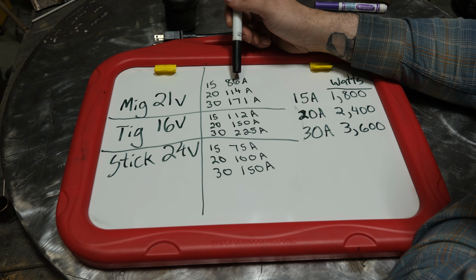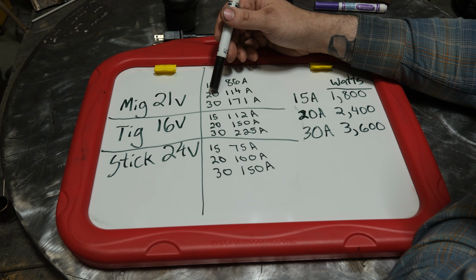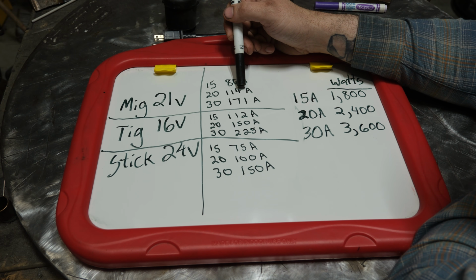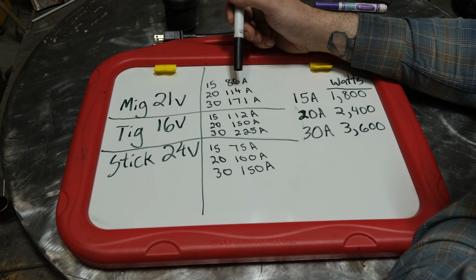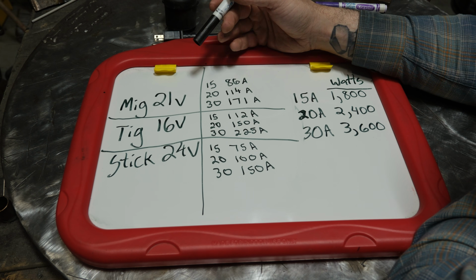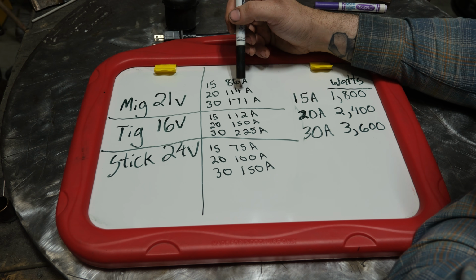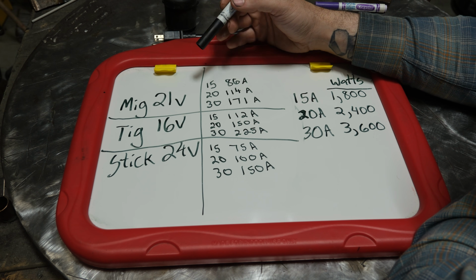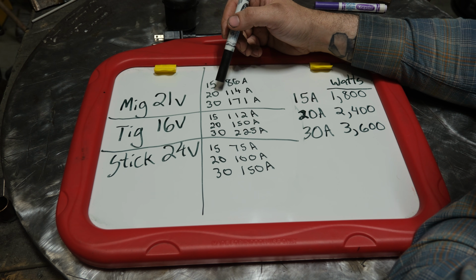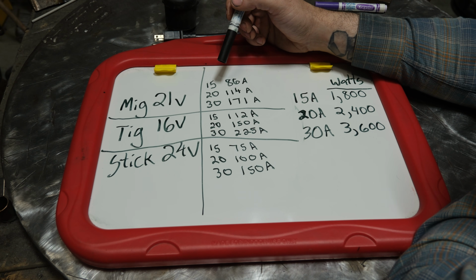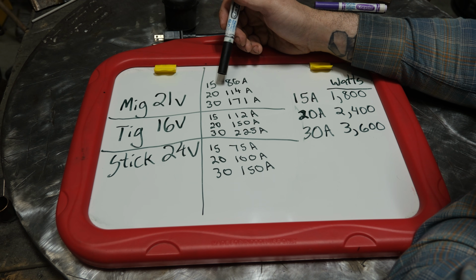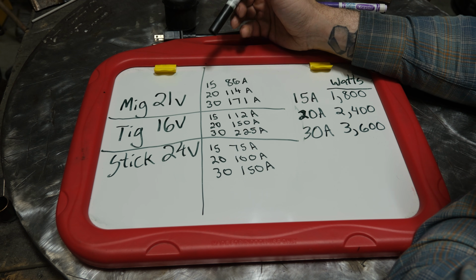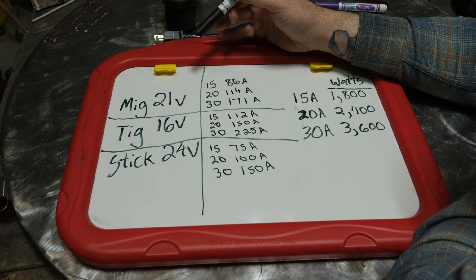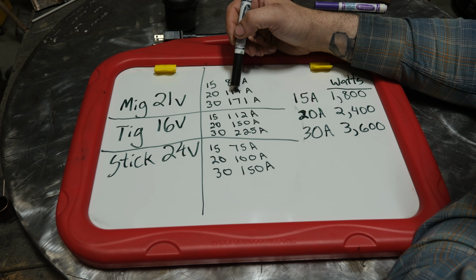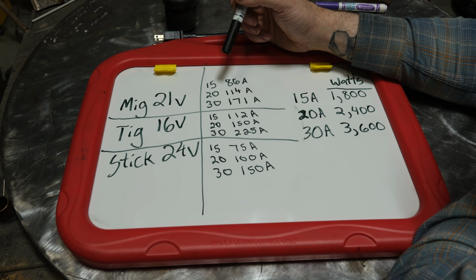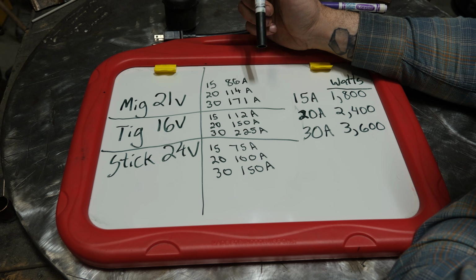On a 15 amp breaker, it's 86 amps. On a 20 amp breaker, 114. 30 amp, 171. Now you're probably asking yourself, well, that's a load of BS, because I have a Lincoln Electric 140 amp MIG welder that's rated at 140 amps and it runs on a 20 amp breaker no problem. Well, yes, you are correct. However, the reason it operates on that is because it exploits the way that the breaker trips.